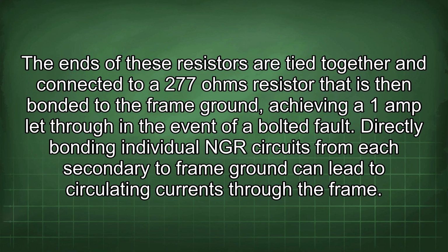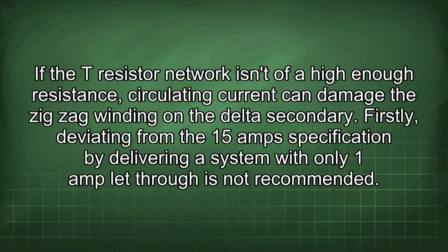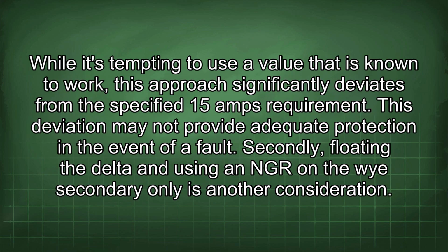Directly bonding individual NGR circuits from each secondary to frame ground can lead to circulating currents through the frame. If the T resistor network isn't of a high enough resistance, circulating current can damage the zigzag winding on the delta secondary. Firstly, deviating from the 15 amp specification by delivering a system with only 1 amp let-through is not recommended. While it's tempting to use a value that is known to work, this approach significantly deviates from the specified 15 amps requirement. This deviation may not provide adequate protection in the event of a fault.